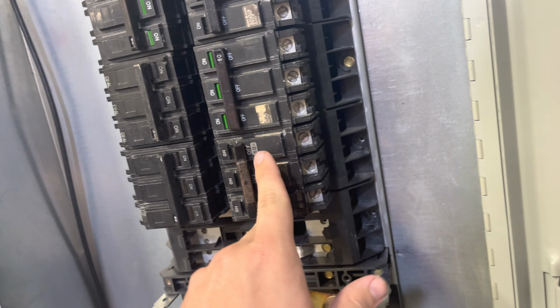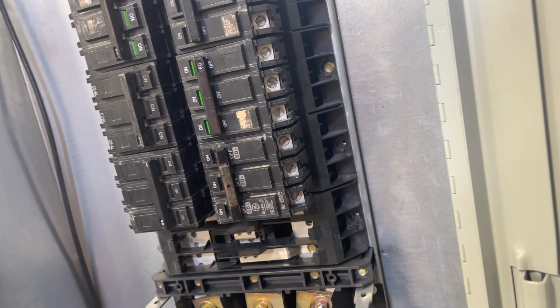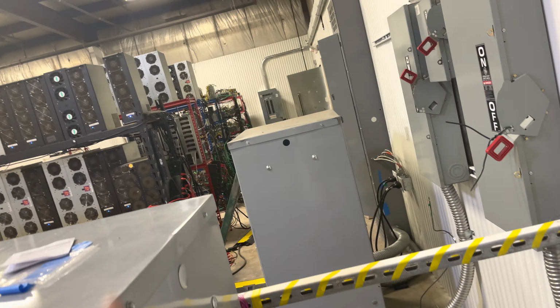These are all 3-phase 80 amp breakers, so each breaker will be able to do like the same as 4 or 5 of those PDUs over there. So that's a pretty big upgrade.